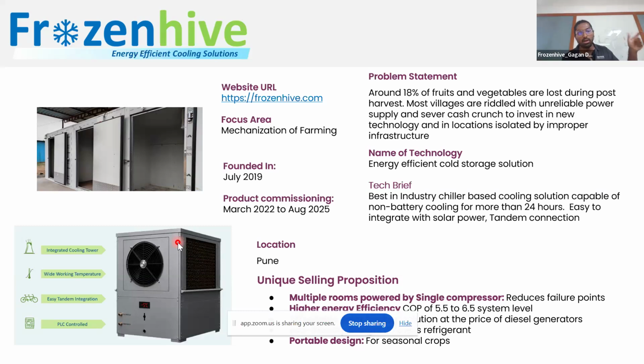It's like the coolers you might be using in your rooms—there's no compressor, but due to the evaporation of the water, there is a reduction in the ambient temperature. If your ambient temperature is around 45 degrees, the first stage of cooling brings it down to around 22-23 degrees. The major heavy lifting is done by evaporation, which makes the whole cooling process very efficient.